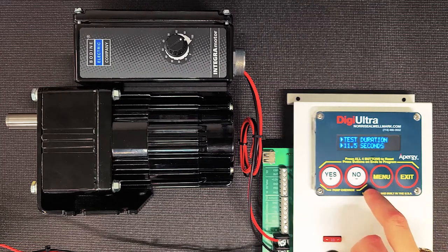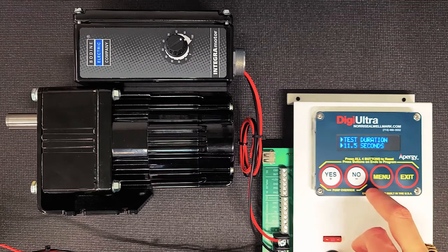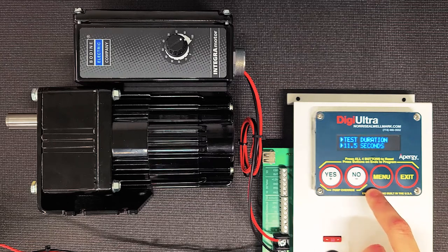And this is where you'll select the test duration. So the critical part of calibrating these pumps is selecting the right test duration. If you have a Kinco 929 rate gauge, which is fairly standard in the industry, depending on the size of the pump, what you want to do is be able to pump that down from the highest point possible that's visible to the lowest point possible in the same calibration routine. So for instance, for a 3/8 inch plunger single head pump on that standard Kinco, starting around 10 seconds would likely be a pretty good starting point. If you accidentally make a mistake or you pump too far or not enough, you can always rerun this test pretty easily.